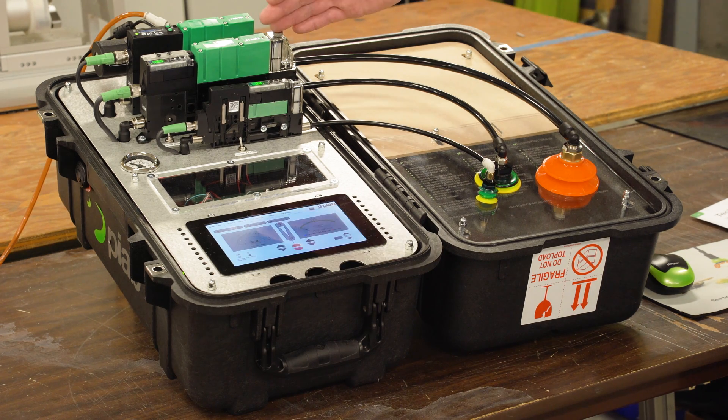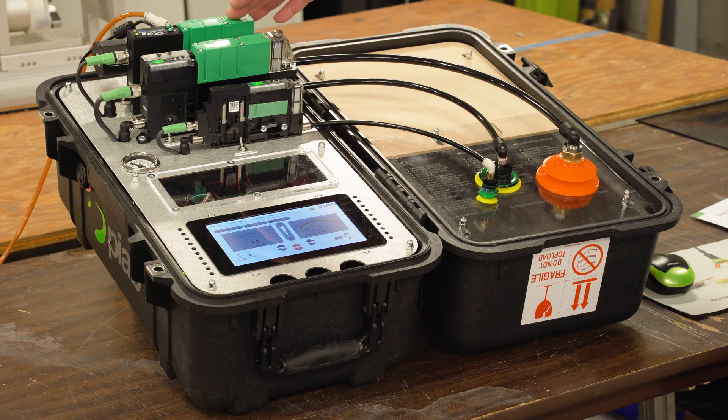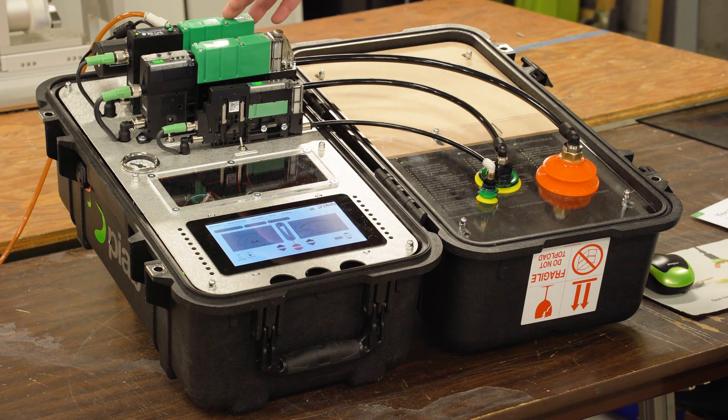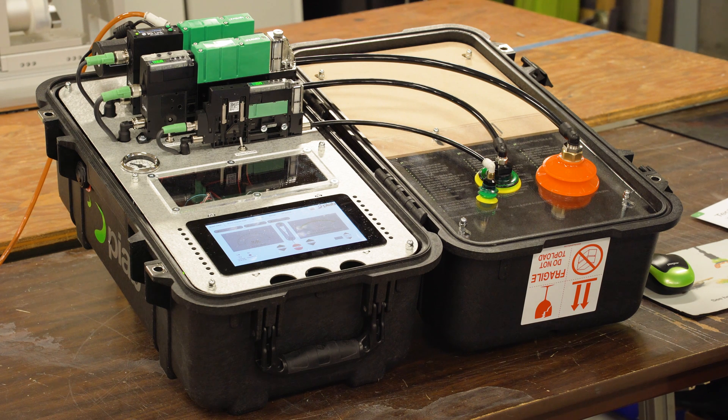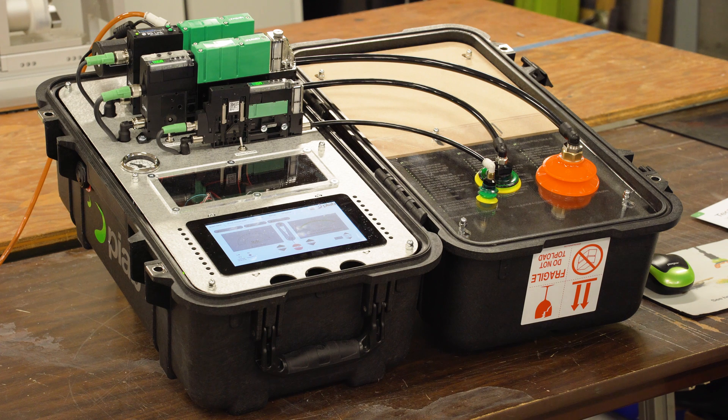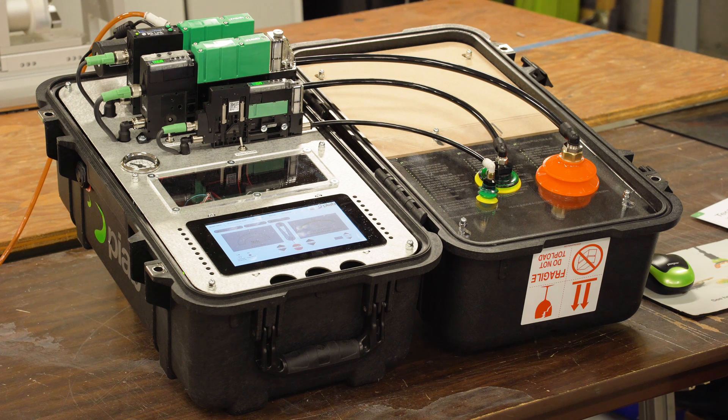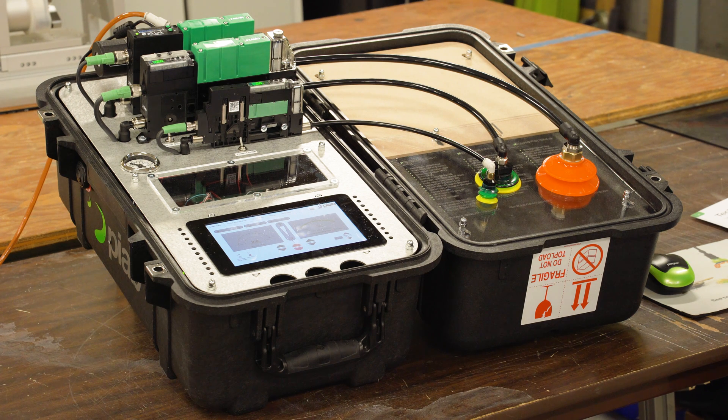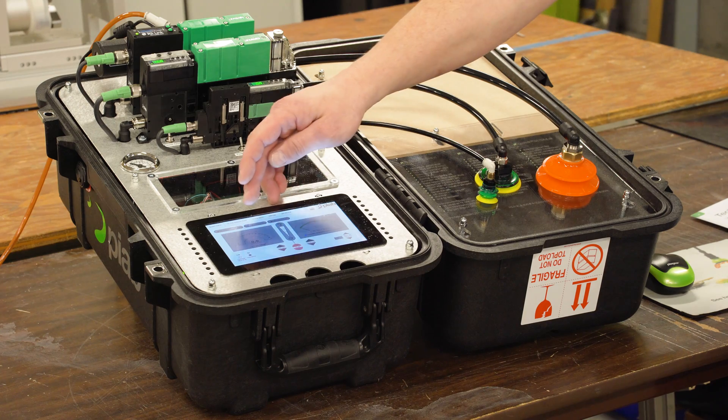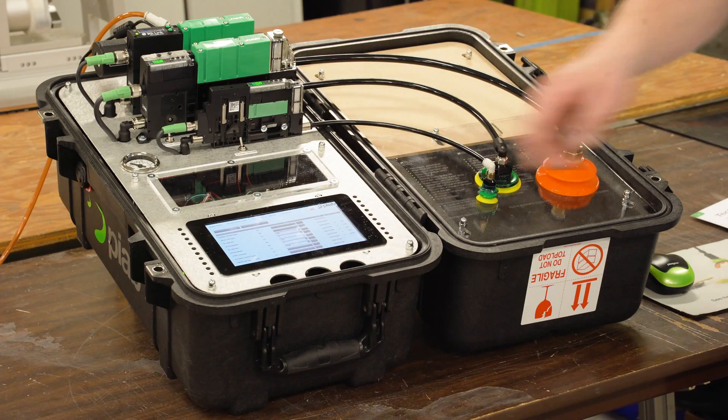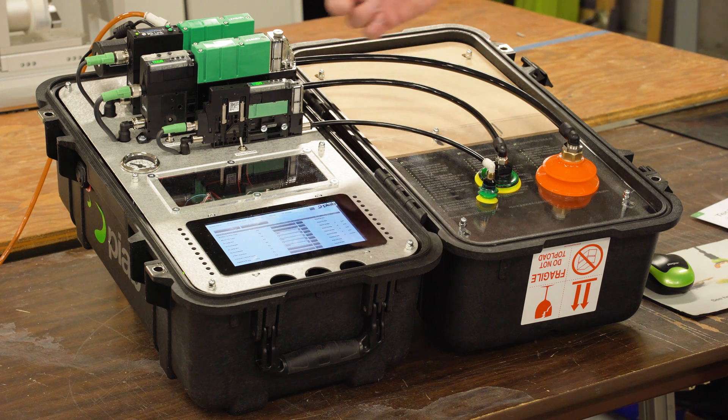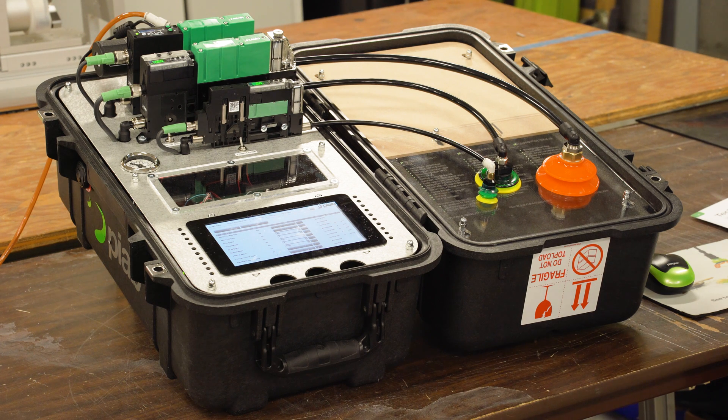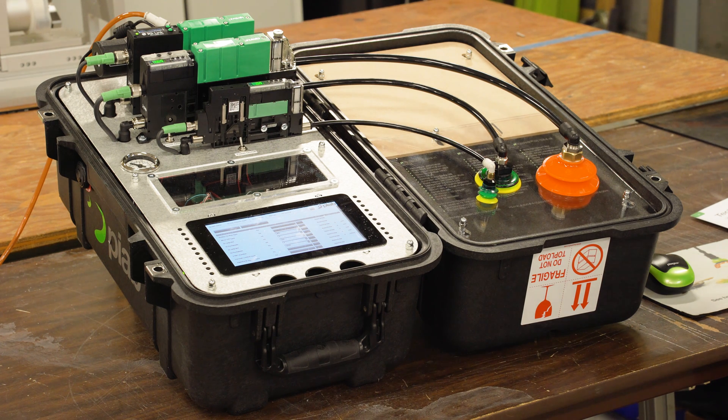So to expand from the Pi Compact 23X, we add IO-Link, the new Industry 4.0 path that everything's going. The nice thing about the IO-Link is I can do all my setup parameters. If it's PNP, NPN, that auto level sensing, if I want to turn energy saving on or off, do I want to have auto blow-off, do I want to have intelligent blow-off, that's all set through your IO. Completely configurable from your controller. You have the whole window of options to establish through IO-Link, and it can change on the fly. So now it's a parameter change that you can push out instantly.